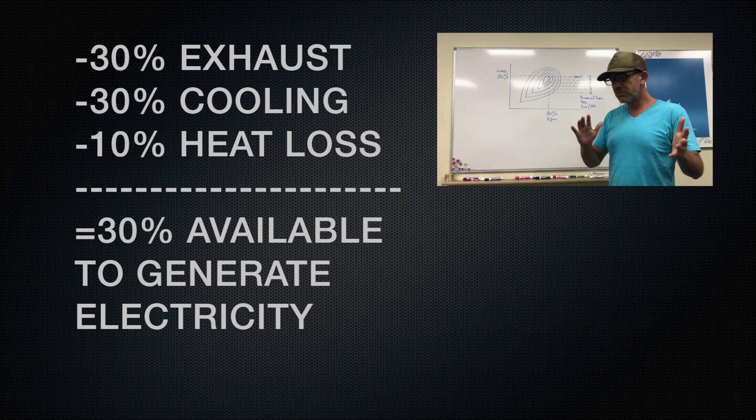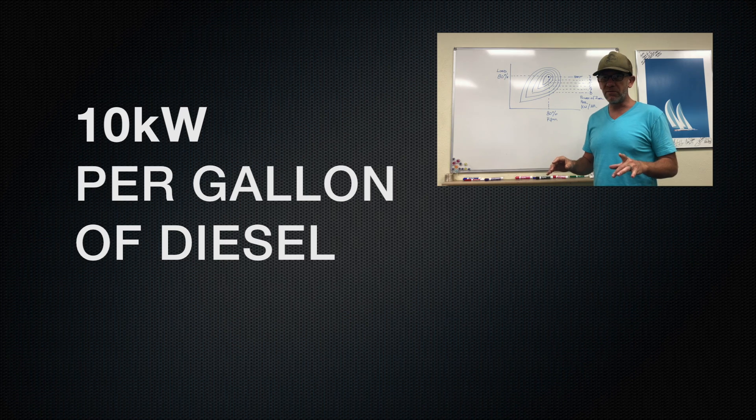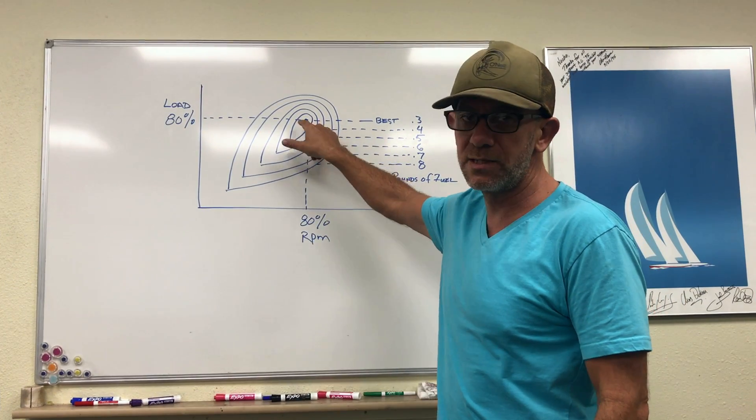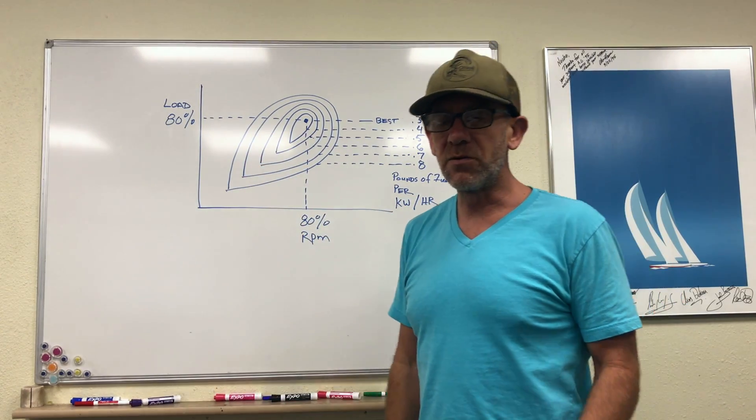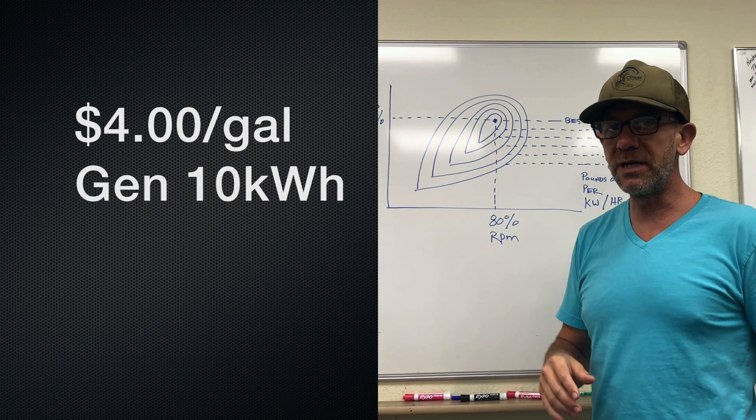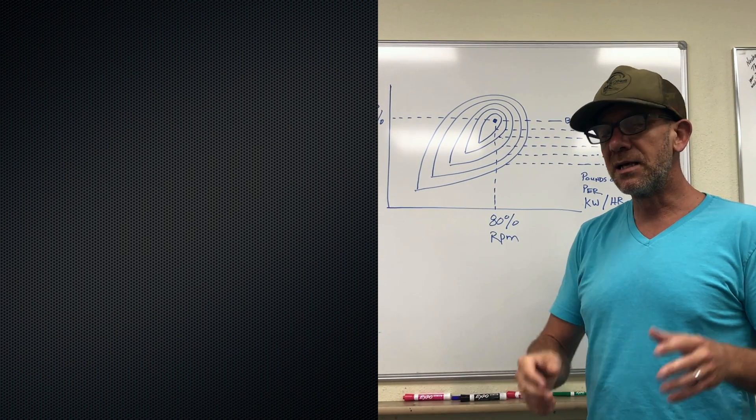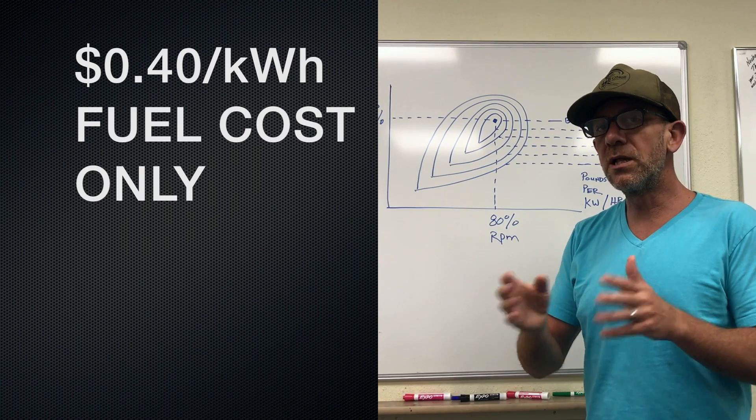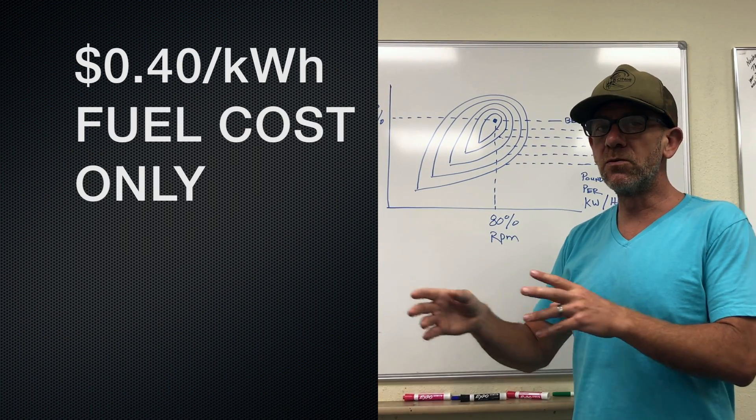Let's just say, to keep numbers round, that ends up being about 10 kilowatts of power that you have available. And that's what you're generating if you are running right at this sweet spot. So if you're buying the fuel for four dollars a gallon and you're able to generate 10 kilowatts of power, that's 40 cents per kilowatt just in fuel cost.